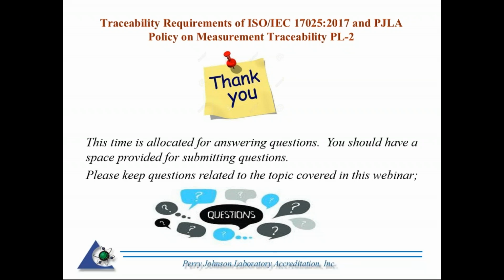If you're just verifying, and I just went through this a little bit ago, it's a little bit different than a calibration. You could do an in-house calibration. It could be traceable, but then it would be assessed just like a traceable calibration. All right, that looks like about all I have right here. So very specific to temperature calibrations. I hope I answered the question directly to exactly what you were asking in the way it was documented here.